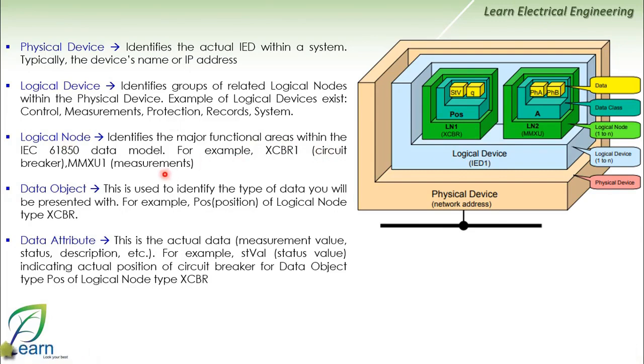What does this mean? For example, if I came to you within these measurements, you would find something called a logical node, for instance, named CMMXU, which is specifically for current measurements. You have, for example, VMMXU, which is specifically for voltage readings, and something specifically for reading residual components. Regarding the phases and voltages, and so on, for example, also XCBR1, which is specifically for the circuit breaker, might be found under control. So we have entered and found a group inside each one, meaning control is not just inside one thing, but a group of them.